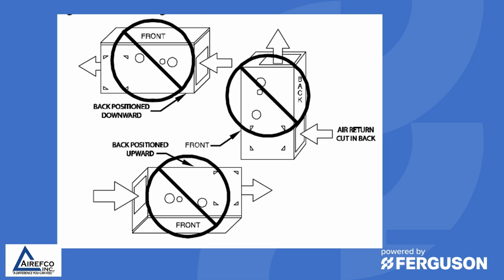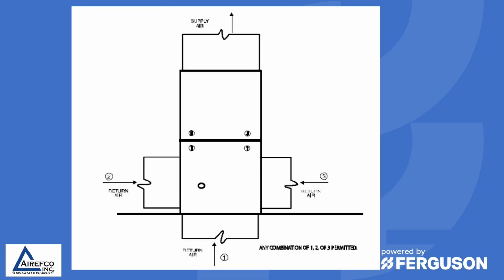Another consideration when installing gas furnaces is the manufacturer's recommendations for the ductwork being attached to the furnace. Many manufacturers in their installation guides have diagrams like this that show that you cannot attach ductwork to the back or to certain sides or positions of the furnace, depending on what configuration the furnace is. So make sure that you check the manufacturer's installation guide to make sure that you're connecting your ductwork correctly to the furnace.